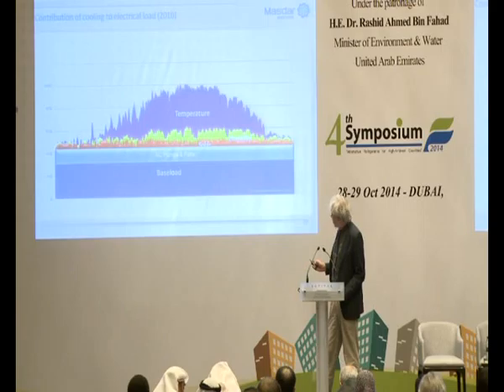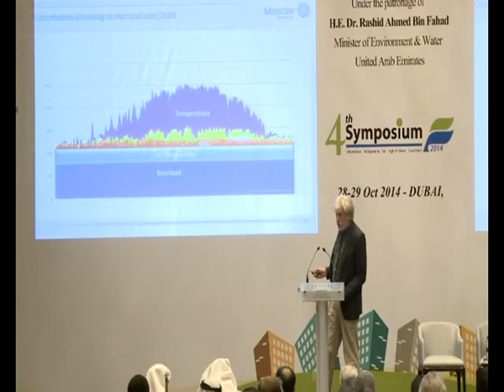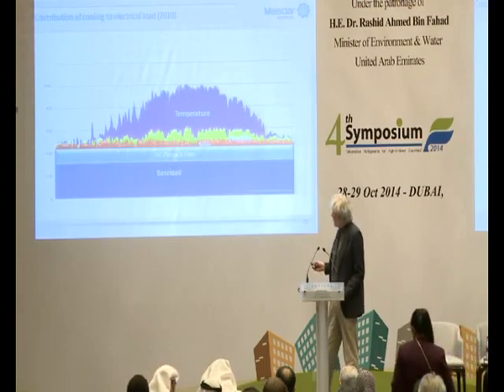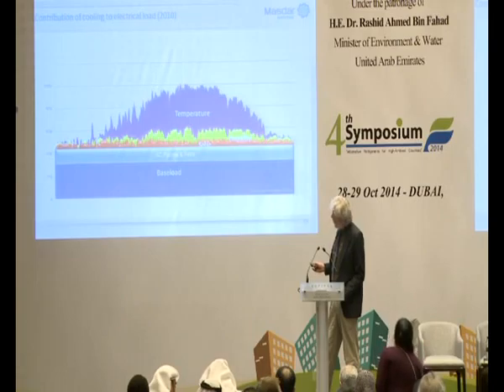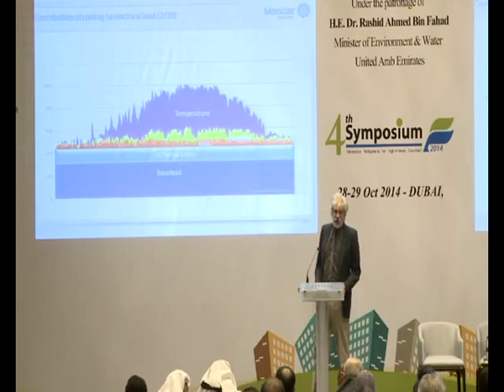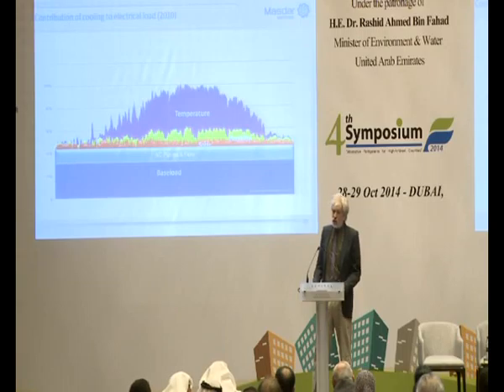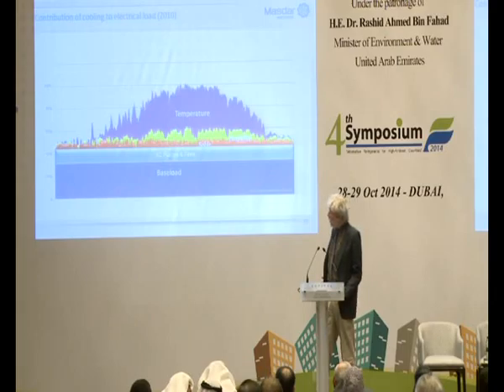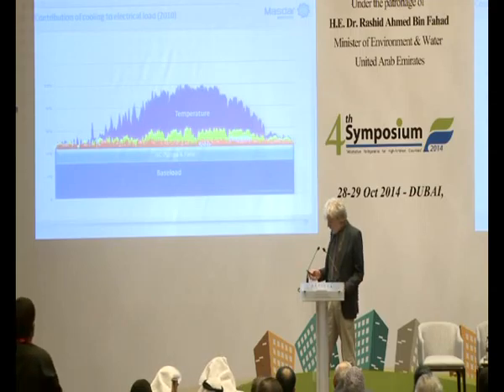We see that solar gains represent less than 20%. That was a bit of a surprise to us. The temperature is over 60%, but humidity is on the order of 20%. That tells us that the leakiness of buildings and the ventilation air conditioning constitute a large fraction of the total cooling. In fact, more like 30%, because of course the ventilation air has to be cooled as well as dehumidified. We'll return to that point a little bit later.